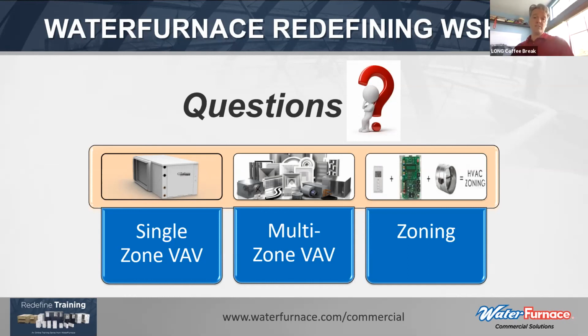Well, and we see a lot of these, especially in schools, done in mechanical hallways and mechanical closets between rooms. You'll have a closet that might have 5 to 10 units as you walk down the line. And those are not just the units themselves, the compressors, the complications, the reversing valves of each one of those units that need to be maintained and looked at, filters and whatnot. But then all the appurtenances that go with them, the hose kits, the strainers, the balancing valves that need to be flushed or maintained over time. So rather than having that little wing of 10 to 15, you might be able to do it with 1 or 2 units, depending on the zoning, and then reduce complication in the entire system. The old keep it simple, stupid principle.